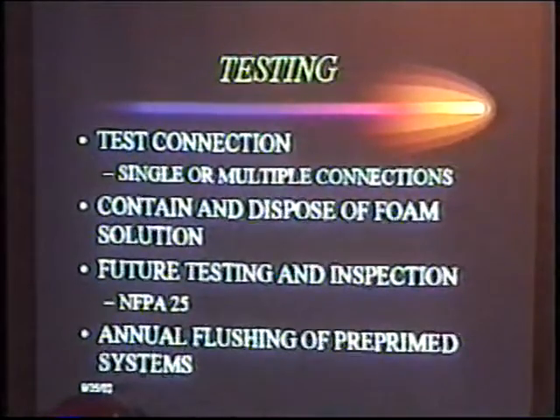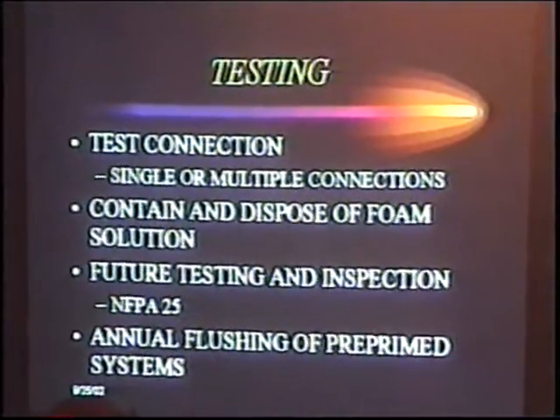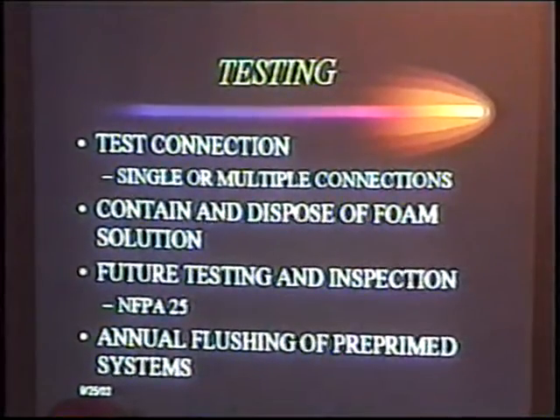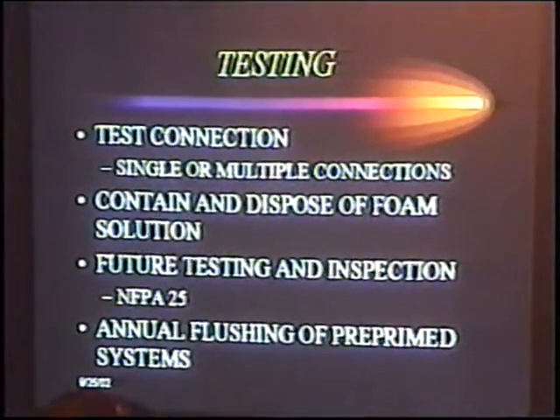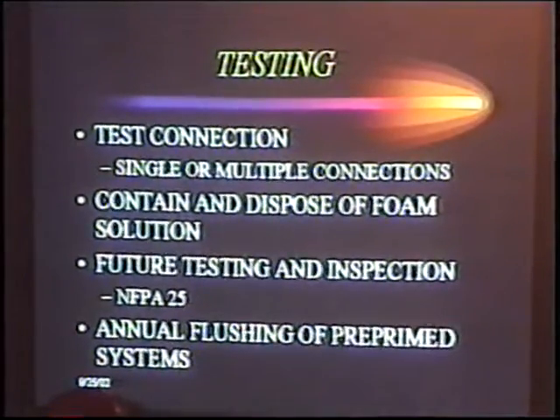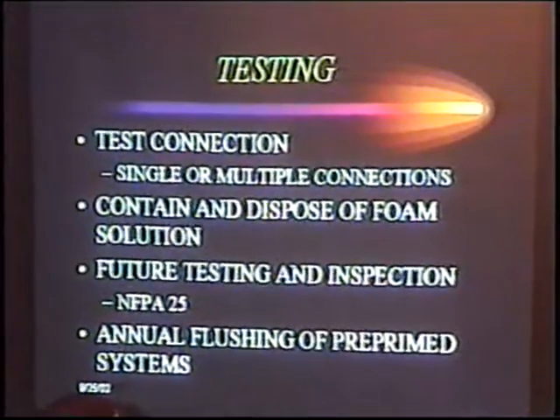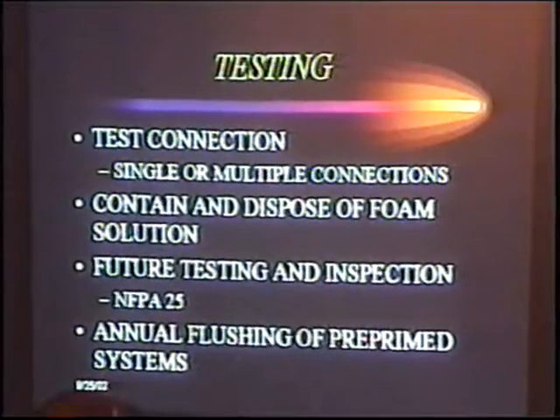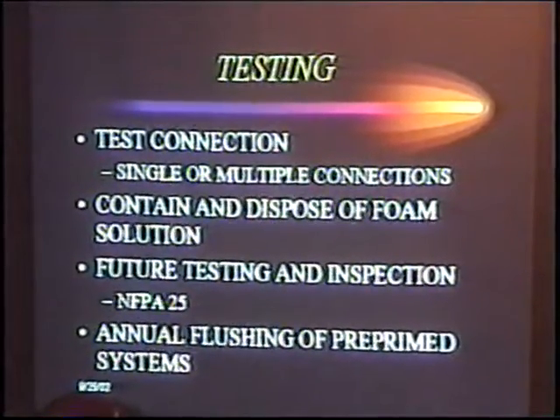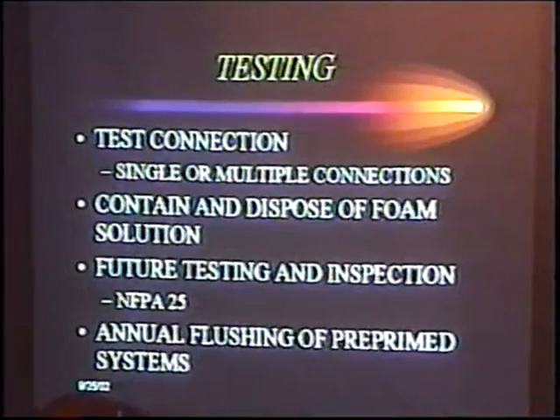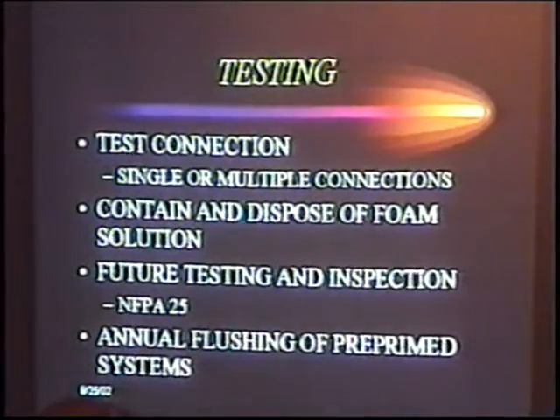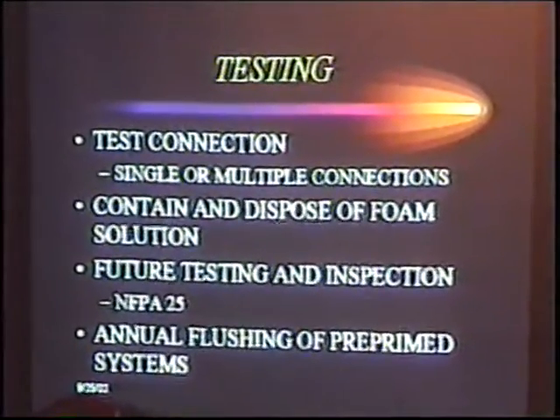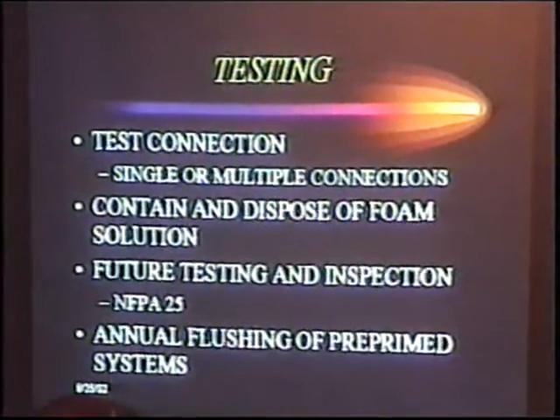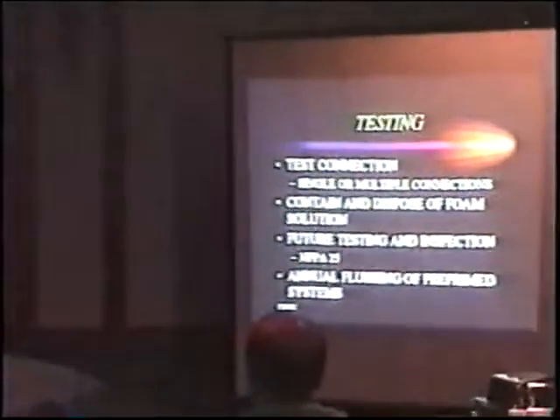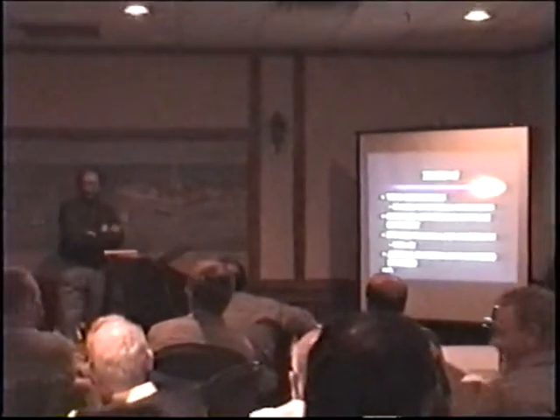Containing and disposing of foam solution, I mentioned that a little briefly, that's almost a necessity these days. Nobody wants to see bubbles coming down the street or coming down the creek. I remember a test up in Washington at an Air Force base. They were telling me about it. A valve didn't close properly and they got foam into a creek. That creek went into the Potomac River and everybody saw it. The EPA was all over them. So for the test that I was out there for, they were running around out on the tarmac with vacuum cleaners, catching any little bubble that was going down. So they were a little sensitive to the situation.